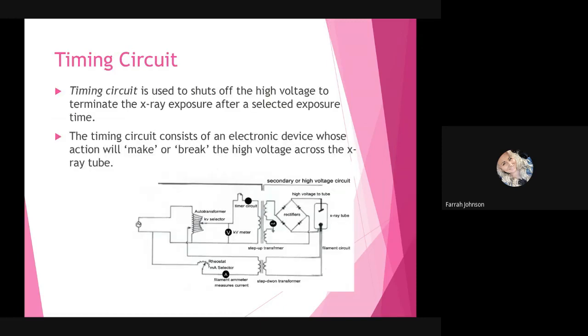So then that brings us to the timing circuit. Your timing circuit is used to shut off the high voltage to terminate the X-ray exposure after a selected exposure time. So when we want our machine to turn off, your timing circuit is what allows it to turn off and not keep irradiating the patient. Now, the timing circuit is going to consist of an electronic device whose action will make or break the high voltage across the X-ray tube. So it basically turns it on, turns it off. That's the whole purpose of the timing circuit.